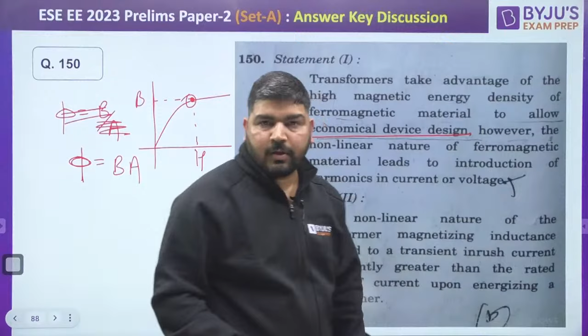Now let's come to statement 2: the nonlinear nature of the transformer's magnetizing inductance can lead to transient inrush current significantly greater than the rated value upon energizing the transformer. That's correct too. The inrush current comes because of the nonlinear nature of the magnetization curve, or magnetizing inductance. So statement 2 is correct, but it is not the correct explanation, because statement 2 discusses inrush current, which has nothing to do with harmonics. Inrush current is a transient phenomenon and harmonics is a steady state phenomenon, so there is no link between the two statements, but both are correct.